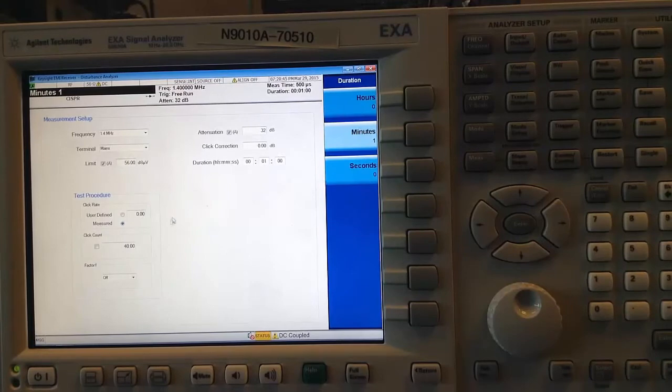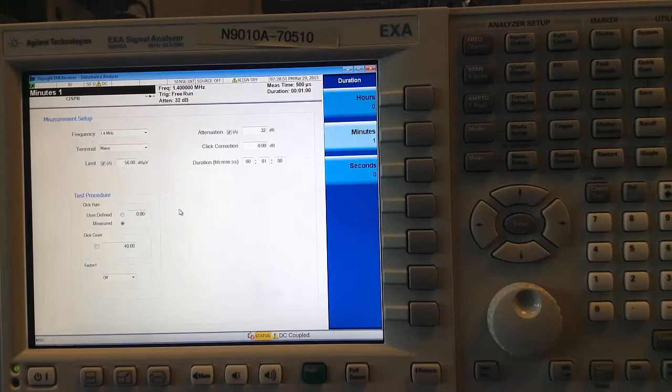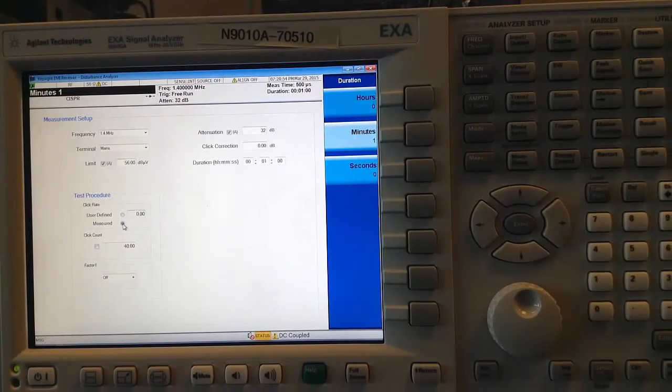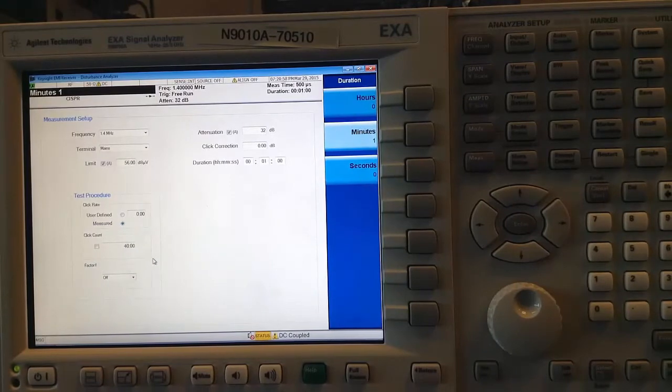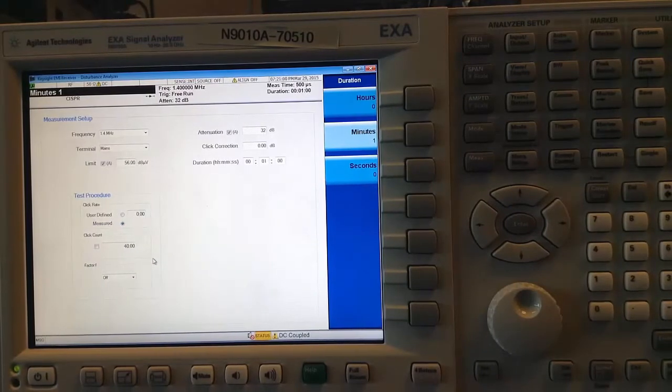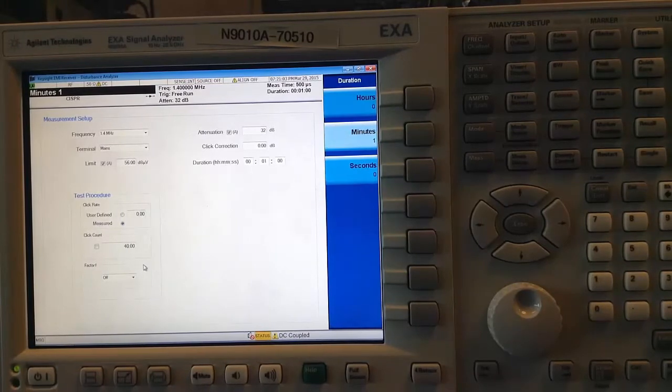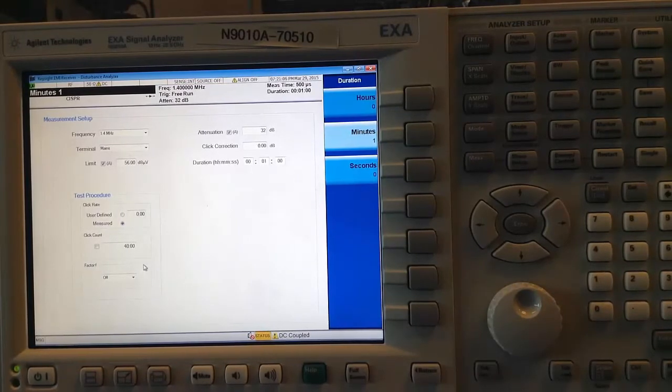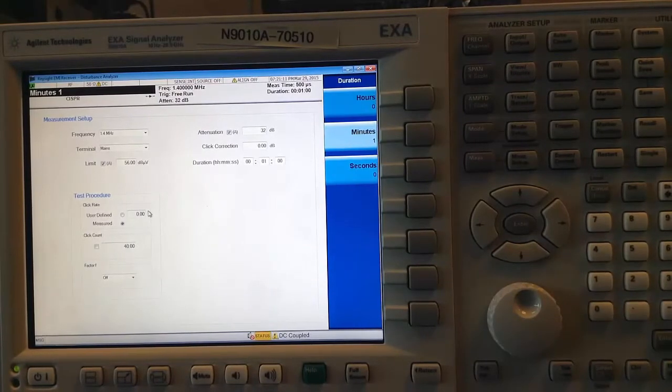Click rate is a metric that is used to define the relaxation on the limit for click measurements. The application calculates the value for you using the measured number of clicks, the factor F if specified, and the formulas given by CISPR 14 to do this. Factor F is also defined by CISPR 14-1 and its use depends on the device under test. You can also set the click rate to a specific value if you wish.